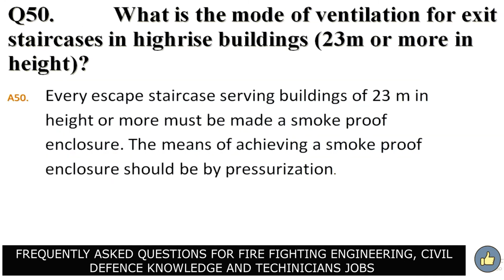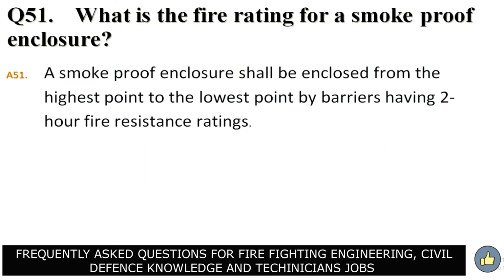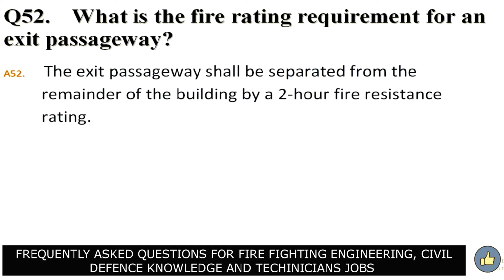What is the mode of ventilation for exit staircase in high-rise buildings 23 meters or more in height? Answer. Every escape staircase serving buildings of 23 meters in height or more must be made a smoke-proof enclosure. The means of achieving a smoke-proof enclosure should be by pressurization. What is the fire rating for smoke-proof enclosure? Answer. A smoke-proof enclosure shall be enclosed from the highest point to the lowest point by barriers having 2-hour fire resistance ratings. Question number 52. What is the fire rating requirement for an exit passageway? Answer. The exit passageway shall be separated from the remainder of the building by a 2-hour fire resistance rating.